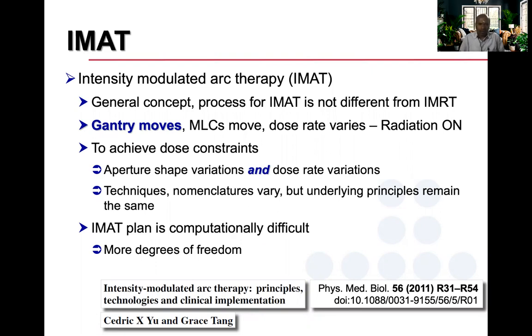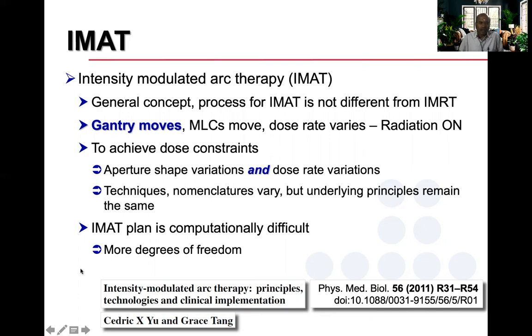Most often we use volumetric modulated arc therapy. The general concept for IMAT is not much different from IMRT. The key difference is that the gantry moves — as against IMRT where the gantry remains static — the gantry moves, MLCs move, and the dose rate is also varied when radiation is on. Aperture shape variations are used to achieve the dose constraints.